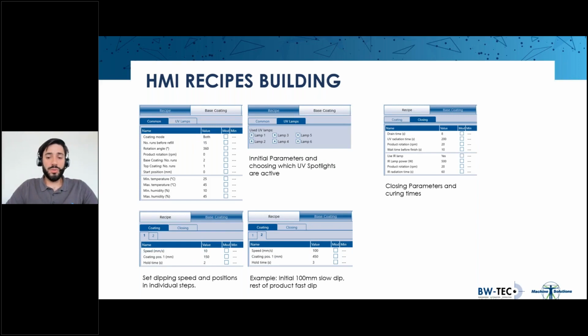Here are some more examples from the recipe creation, showing which options you have. To save on UV hours, you can specify which lamps should be used in the process. For example, if you do a development batch and are just doing one rack at a time, you can select just 2 of the 6 lamps to save the others.